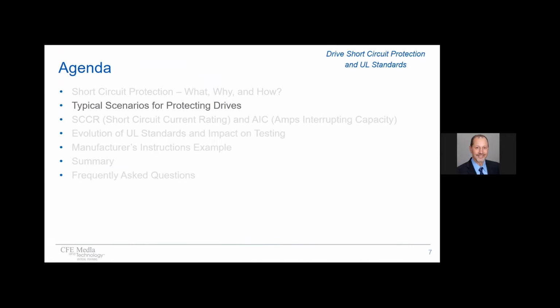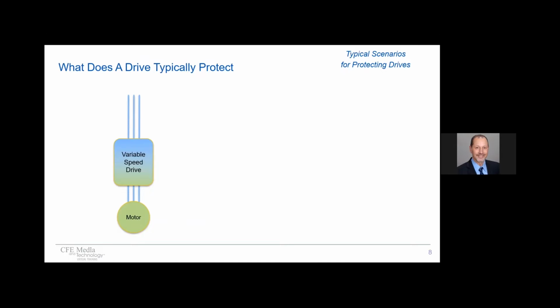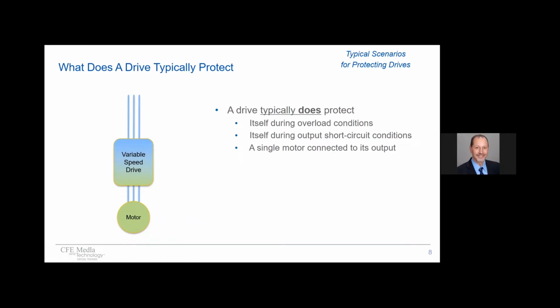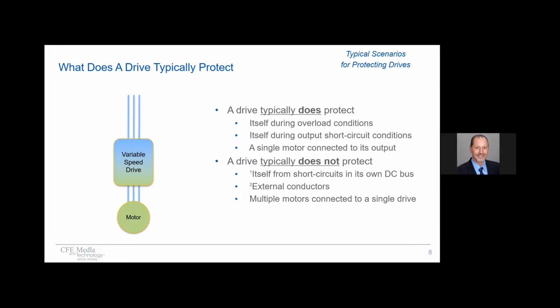So let's look at some typical ways of protection when applying variable speed drives. First off, a drive itself typically has protection for some conditions. A drive typically protects itself during overload conditions. It also protects itself during output short circuit conditions, and I'll stress the word output there. It also usually protects motors. But what it typically does not protect is itself from internal short circuits in its own DC bus. It also typically does not protect external conductors, nor multiple motors connected to a single drive, typically.